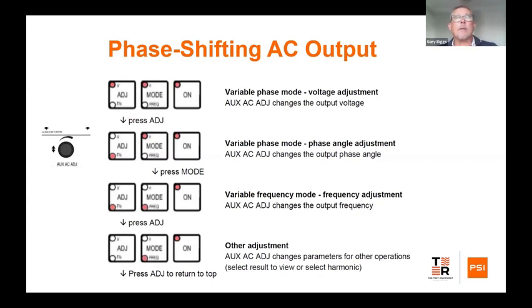This is just a little diagram of how we control that auxiliary output. As you can see here, we have red lights on the buttons. When we press the button, it will switch. In the case of the first button that we can see here, the adjustment button, we can either select voltage or frequency. Here we can select phase or frequency, and when we turn that on, that will actually adjust whatever we set. And this just gives you a key when you're using our test sets as to what we're looking to control.